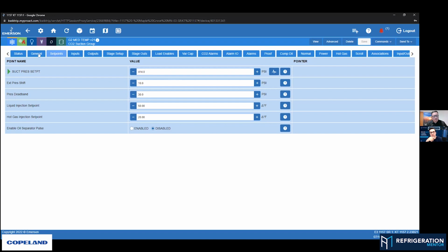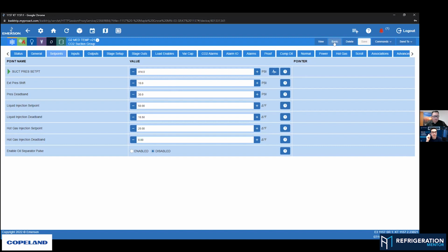Let's just dive into this, because I see the hot gas injection set point is 20 degrees. So at 20 degrees, when you start to get below that, it's like okay, we need some hot gas injection. What would that be connected to - like what board point? I know it's a solenoid, assuming it's a solenoid, but give some people an idea on the concept of what's happening with that.